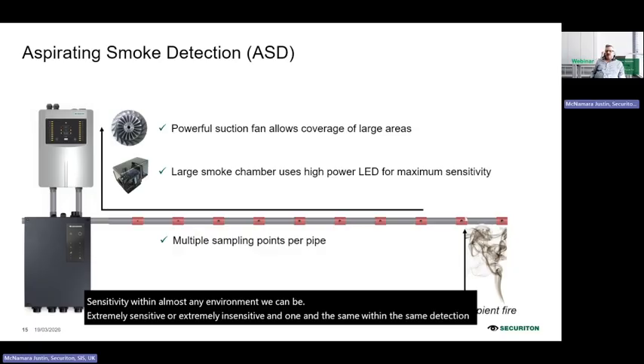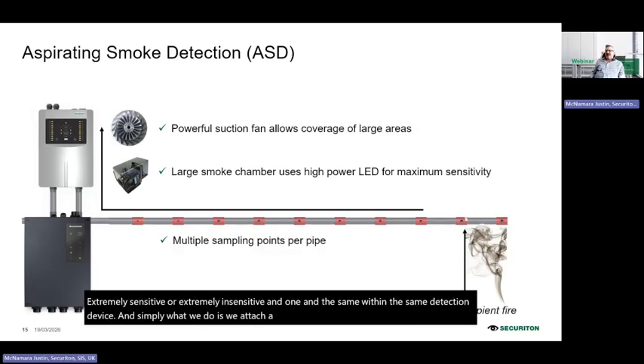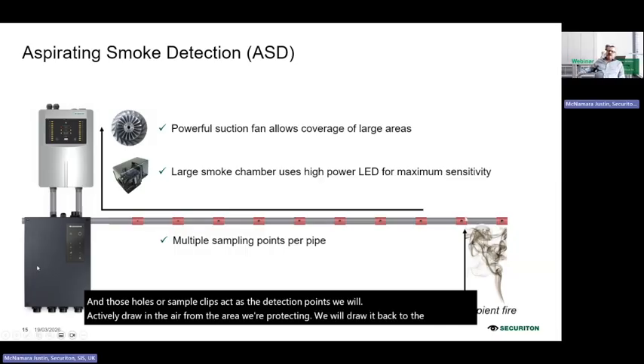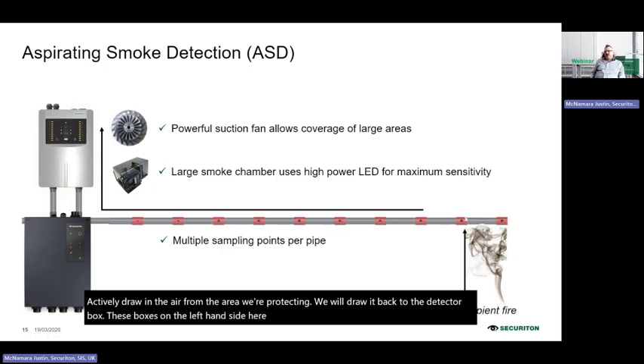And simply what we do is we attach a tube or tubes to these ASD boxes, and typically we will drill sample holes or attach sample hole clips to that tube, and those holes or sample clips act as the detection points. We will actively draw in the air from the area we're protecting. We will draw it back to the detector box, these boxes on the left-hand side here, and analyze what we can see. And then obviously, if we can see some smoke particles, we will trigger alarms accordingly. Very simple, but very clever technology.